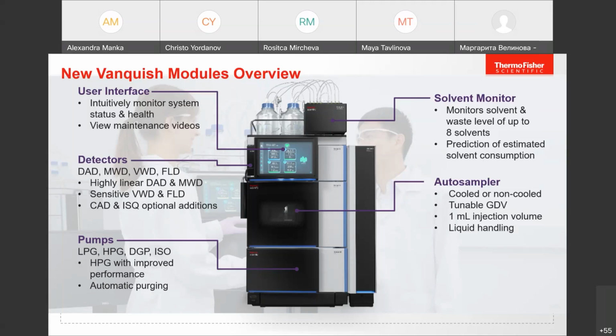In the middle, you have the autosampler. Here we have a cooled or non-cooled version with a tunable gradient delay volume. I will show you this a little bit later. It can do up to 1 mL injection, and we have what we call liquid handling. So you can do user-defined programs or liquid handling that you might know from Ultimate 3000 samplers already. And then on the right side, you have the column compartment. This one can go up to 85 degrees C. We have an optional active preheater, and in this column compartment, you can also install our method transfer kit that I will show you in a couple of minutes.